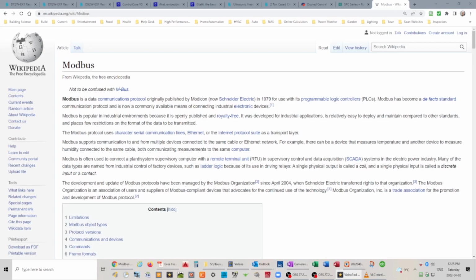In our case, we're using Ethernet cables between most devices. It also supports communication to and from multiple devices on a single cable daisy chain. This level of open source control allows for ultimate flexibility in the control of your hydronic heating and cooling system, something that is just not available with the proprietary systems offered by pretty much any other HVAC equipment manufacturer.